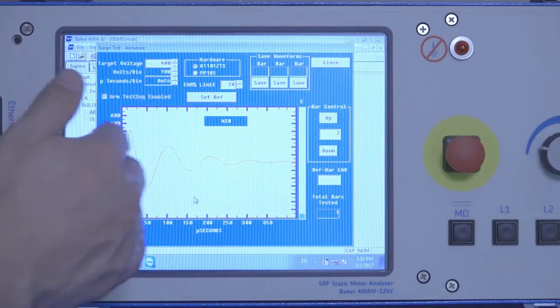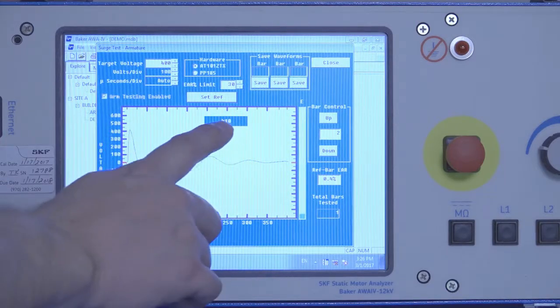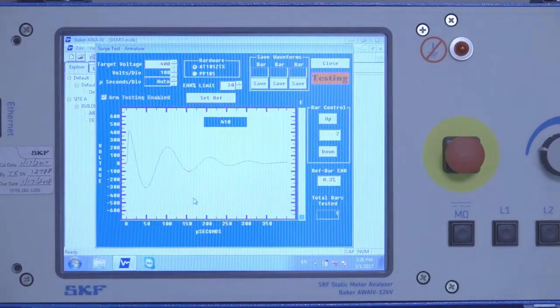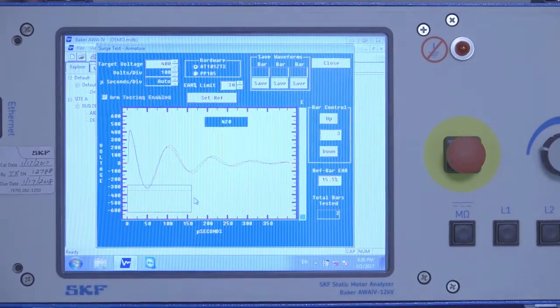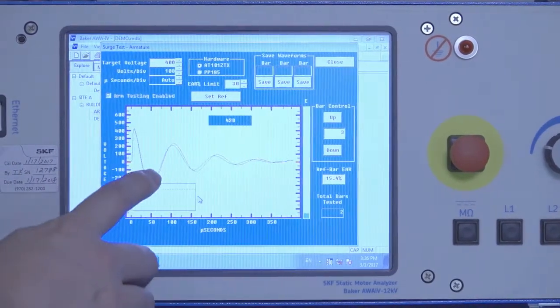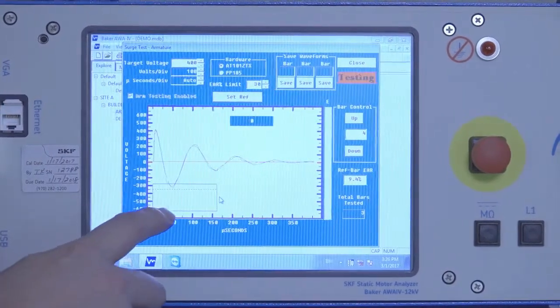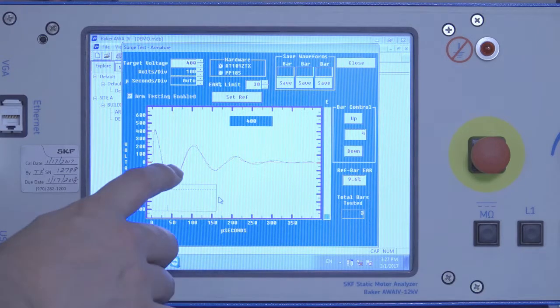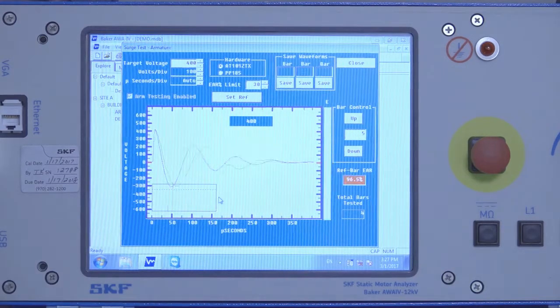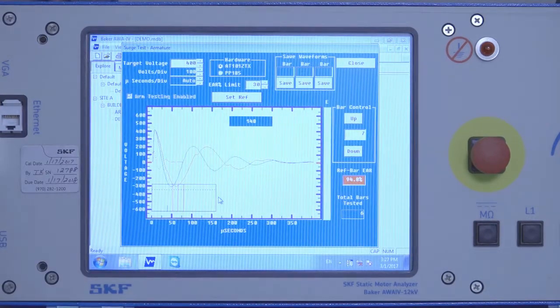Now I'm ready to move on to the adjacent bar, hit the test button again, and the voltage automatically comes right back up to 400 volts. I just continue to move around the armature from bar to bar making waveform comparisons. In the lower left-hand corner, we have the pulse-to-pulse EAR graph giving us a bar to indicate the difference in pattern from one bar test to the next, so we can see the variation in the EAR that's occurring.